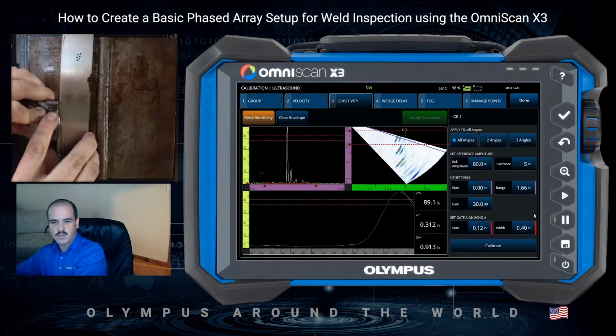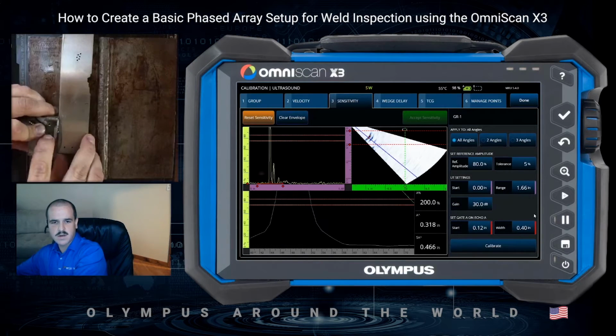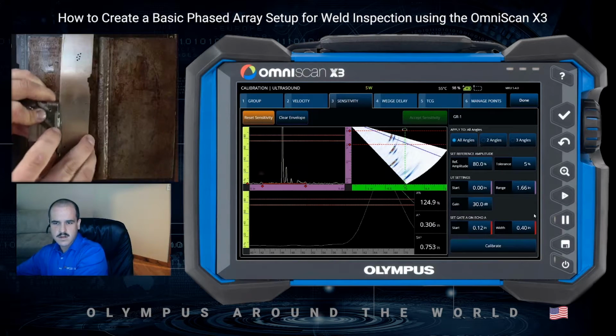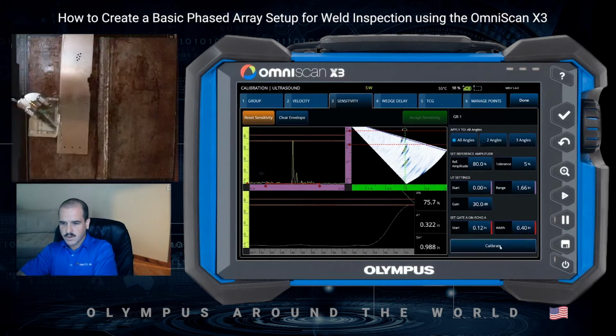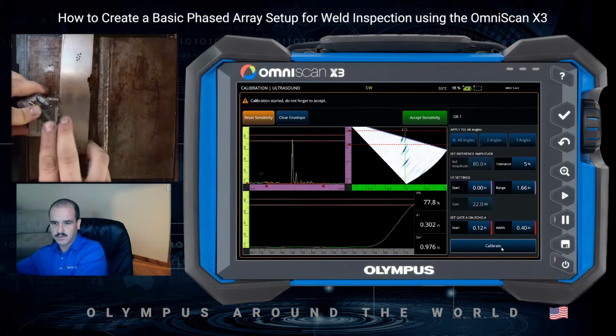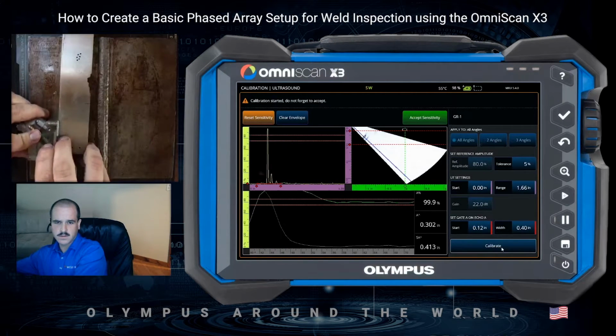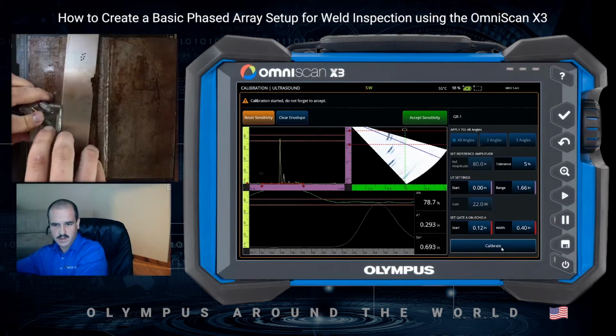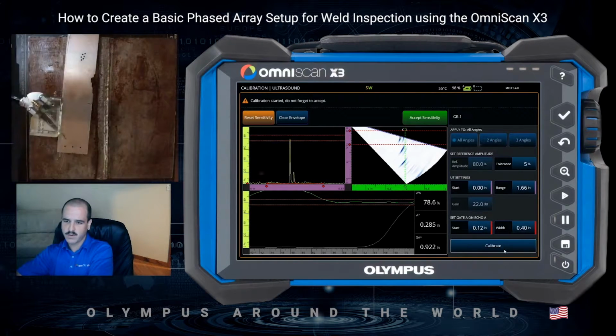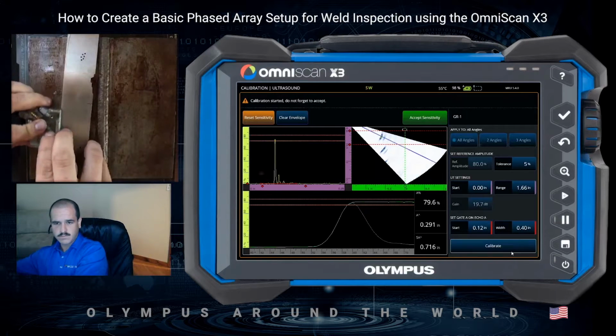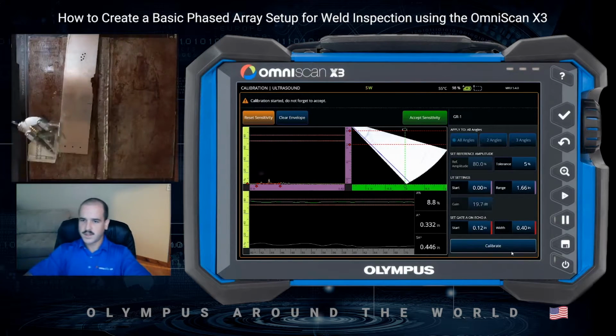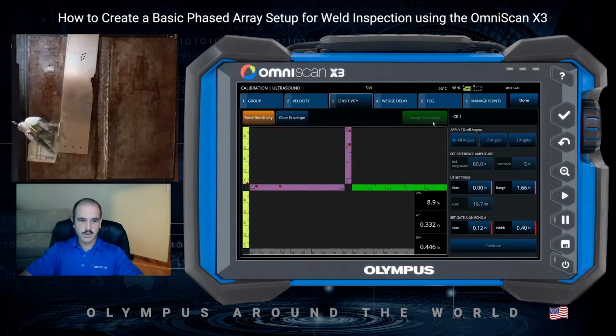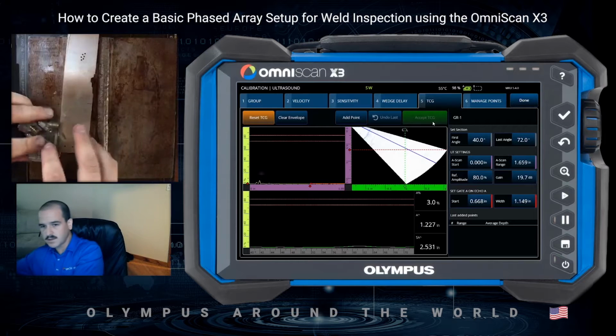So I'll run it back and forth a couple times, make sure I get that signal peaked out. Run the calibration and do a verification. Looks like we're still a little bit hot in the lower angles there, so we'll run it one more time. Looks like our sensitivity calibration is now within our desired tolerance of 5%, so we'll accept our sensitivity and move on to our TCG. So we'll just build a quick 3-point TCG curve here.